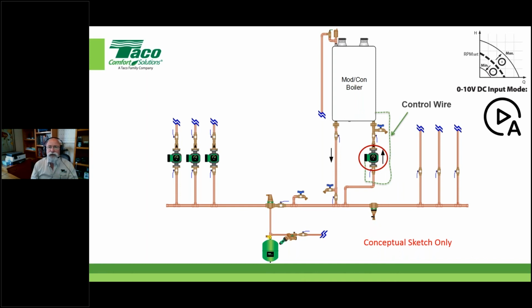The boiler manufacturer always is looking at supply and return temperatures across its heat exchanger. It also, in some cases, has the ability to look downstream, maybe put a sensor out over here and look at the secondary portion of the system. Okay, the system side of things. So again, understand that that's all information that the boiler's making decisions on, and it now has the ability to ramp this circulator up and down to maintain something. The majority of the people that have had success doing this, that input is based on a temperature differential across its heat exchanger. Okay, we know that as a boiler modulates its flame up, we're adding more energy to the fluid within the heat exchanger. Well, the telltale sign of that is a big increase on the supply water temperature.